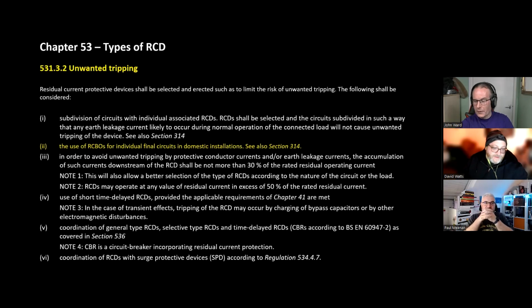So, Chapter 53, types of RCD, 531.3.2. Everything in that is the exact same except for the section in yellow, which says the use of RCBOs for individual final circuits in domestic installations. With that rollout and the 30% maximum leakage current, they have been able to delete or retire certain clauses. So basically, if you want to comply with Section 2, use RCBOs.